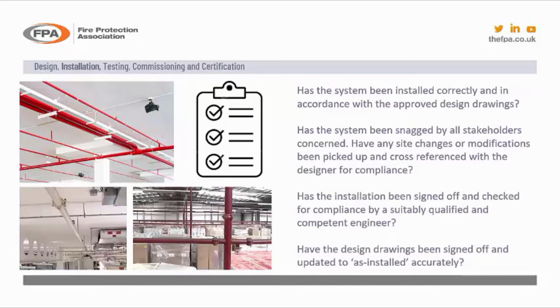If there is a need for a change or modification, this should always be cross-referenced with the design engineer who's designed the system, and he will ensure that the changes comply with the standard. Many times it's happened over the years that a design's gone in and it's been hydraulically calculated, it's been hydraulically balanced, and it's going into drawing, then all of a sudden there's an issue. Something's changed and we've had to do some site modifications, and we've introduced some elbows and some bends, we've dropped down, so we need drain points, and all of a sudden we need to increase the size of the pipe.